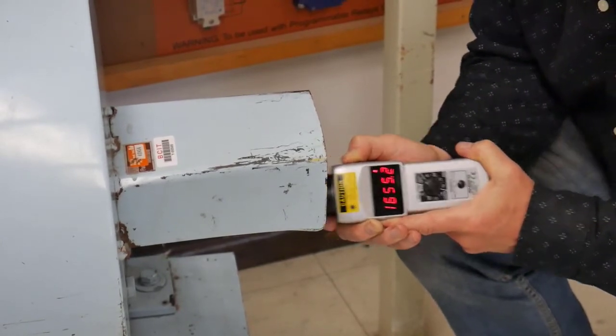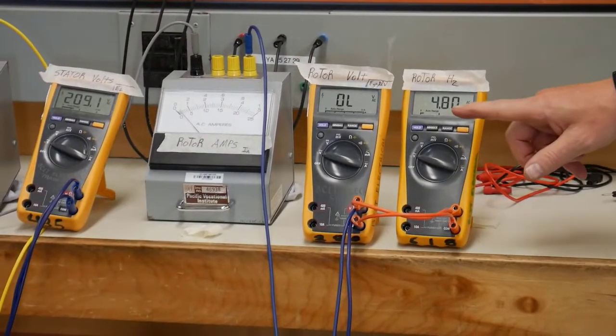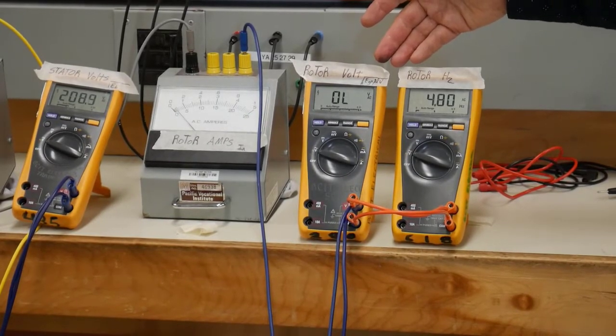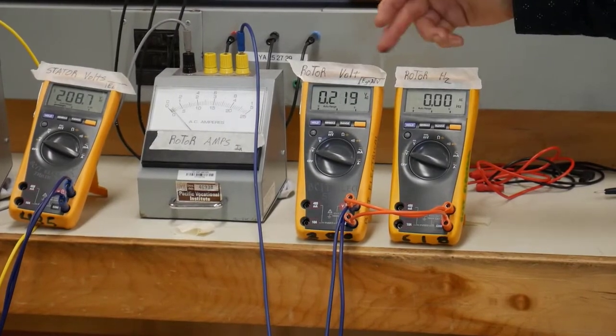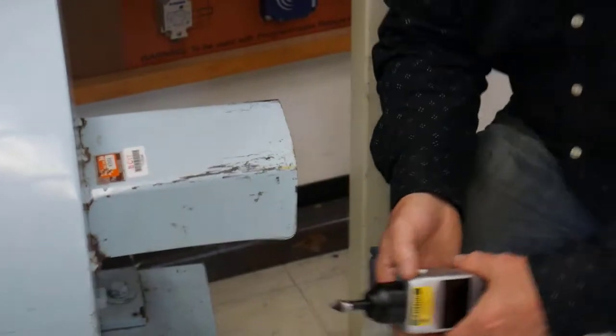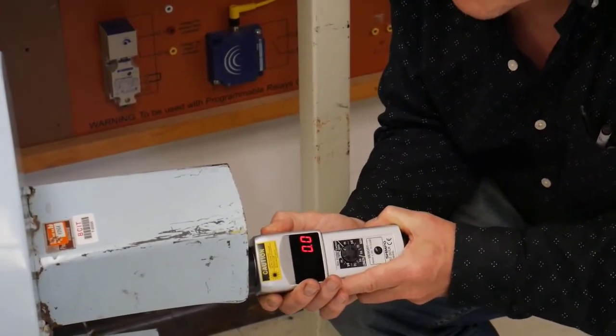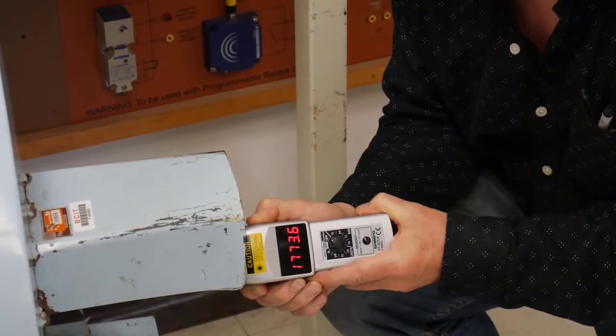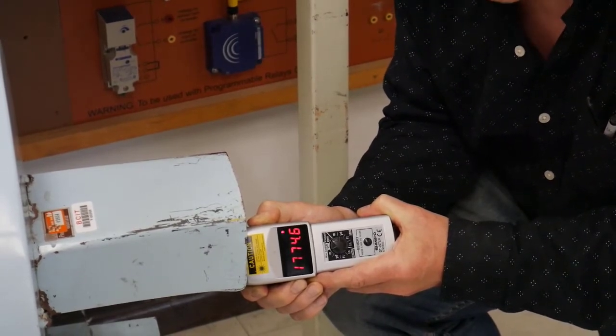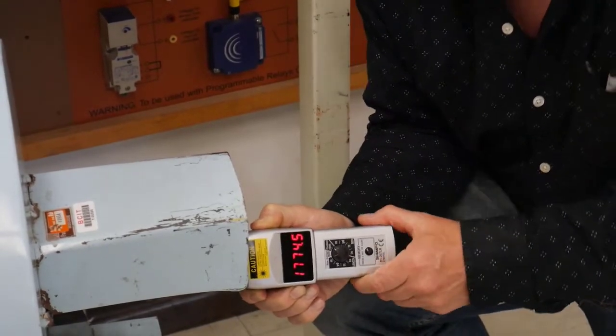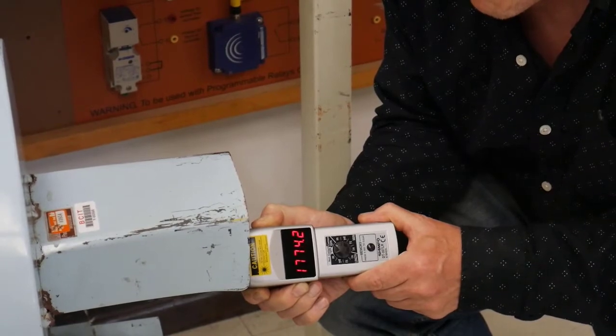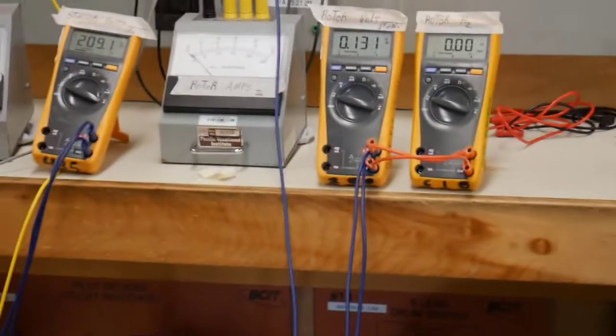Now let's bypass the remainder of our resistances. These are going to drop down to zero hertz and zero volts. The meters are now being bypassed by the contactor, so they're measuring across that jumper again. Our RPM—we now have high enough rotor current to supply enough torque to get our motor up close to full speed. We're at 1774-1775 RPM. The full load rated RPM for this wound rotor motor is 1720, so we haven't quite loaded it up.